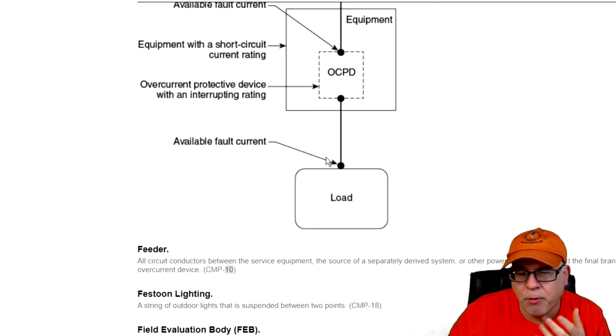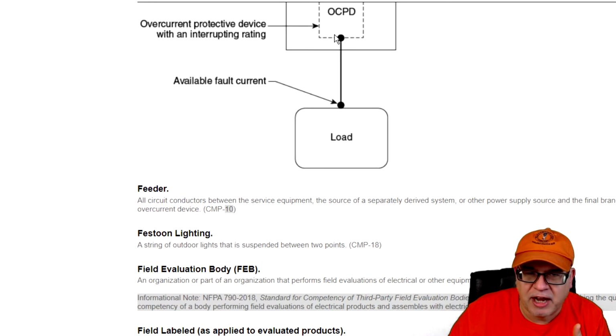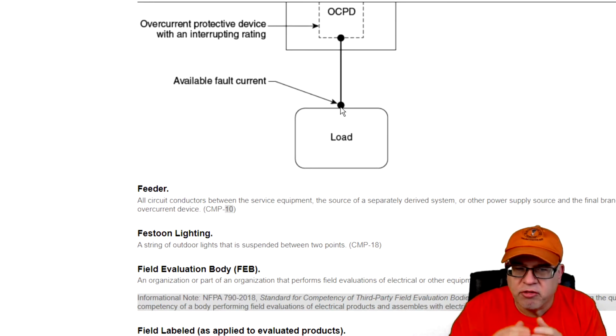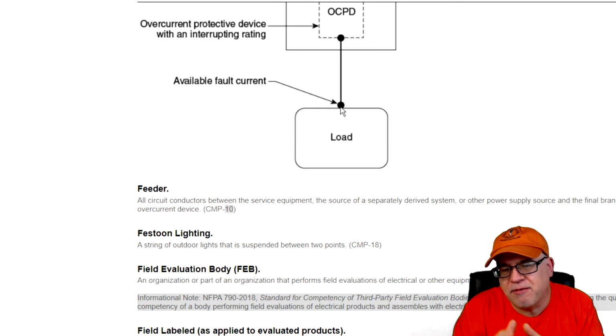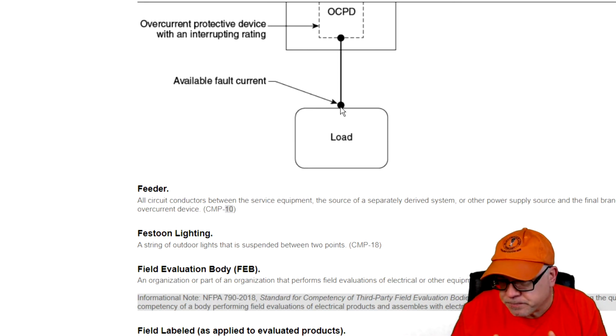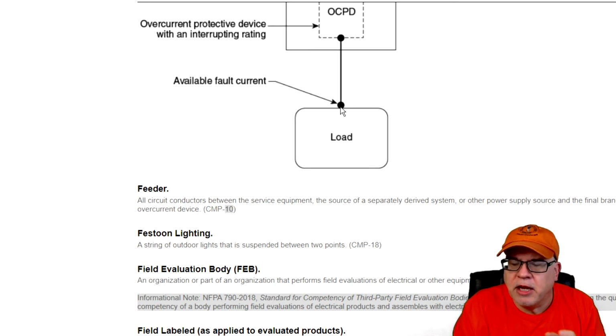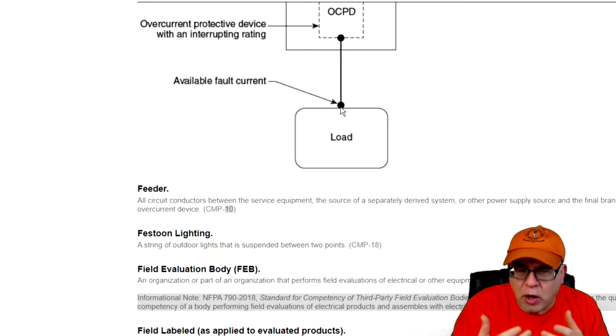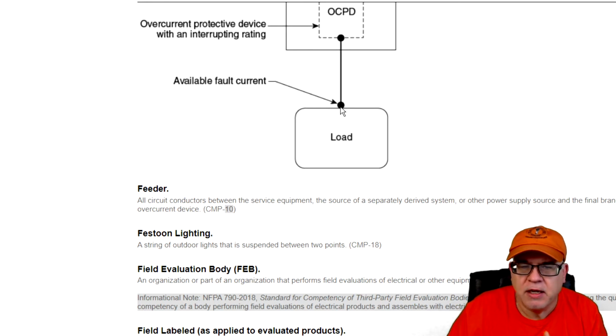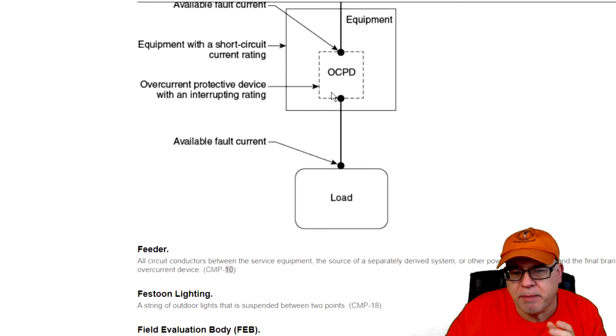be. But important to note that even on the load side, out to a piece of equipment, when you're measuring and your code asks you what the available fault current is, say for an industrial control panel that's downstream, then you need to know what it is at that equipment so that we know what to rate the equipment, okay? So you don't want it blowing up in people's faces.